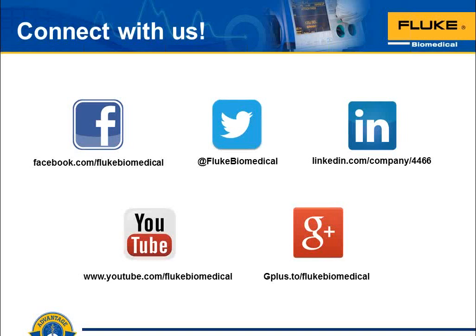Excellent. Okay. The next one that came in is, can I use Ansur test automation with the QA-ES? Absolutely. QA-ES has an Ansur plugin, which means that we've taken care of the device driver. The Ansur template that you create, or a category-specific template that we've already created and provided to you in the Ansur test library with the software, actually reaches out, configures QA-ES2, and collects the measurement values automatically for you. In fact, the Ansur test procedure, that template, can include everything that you're doing. So all of the workflow can be included. And if you have an Ansur plugin for any of our safety analyzers, you can also incorporate that into your workflow. So all of your measurement values can be pulled in automatically, including those ones for argon gas, by the way, if you're using any of our 3 gas flow analyzers.